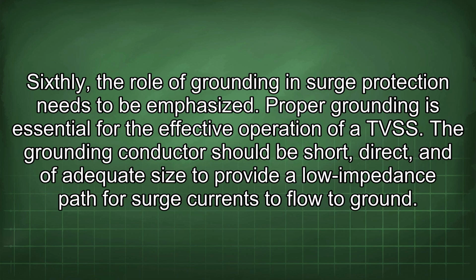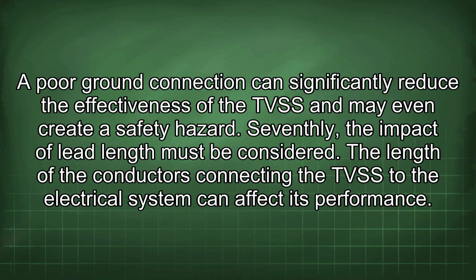Sixthly, the role of grounding in surge protection needs to be emphasized. Proper grounding is essential for the effective operation of a TVSS. The grounding conductor should be short, direct, and of adequate size to provide a low impedance path for surge currents to flow to ground. A poor ground connection can significantly reduce the effectiveness of the TVSS and may even create a safety hazard. Seventhly, the impact of lead length must be considered.